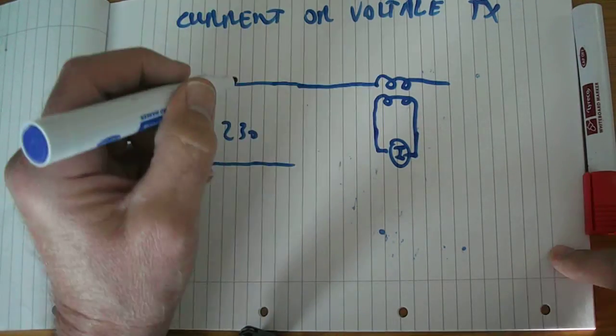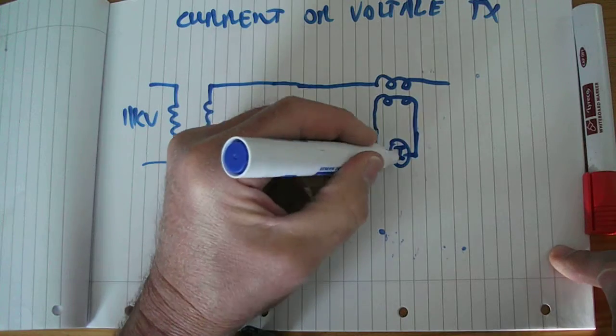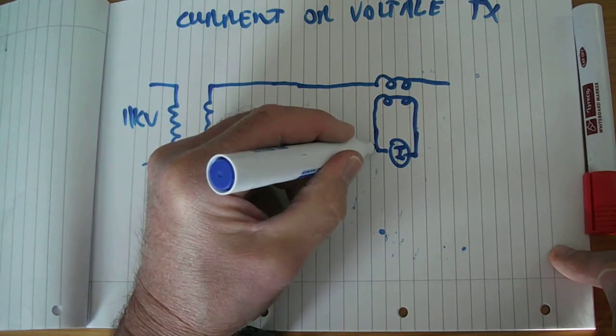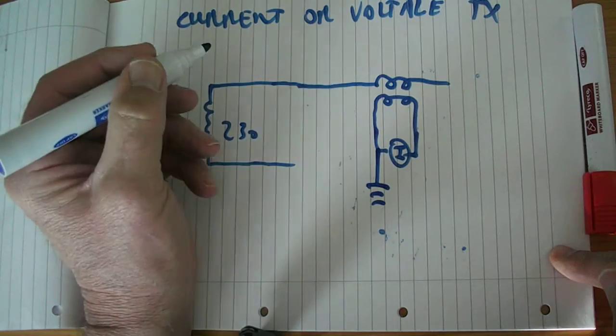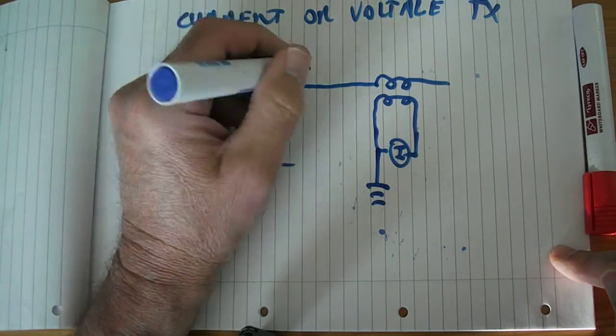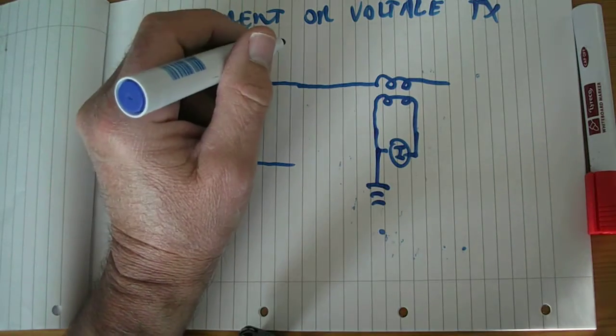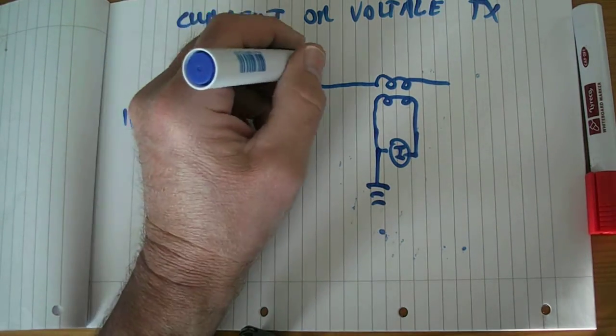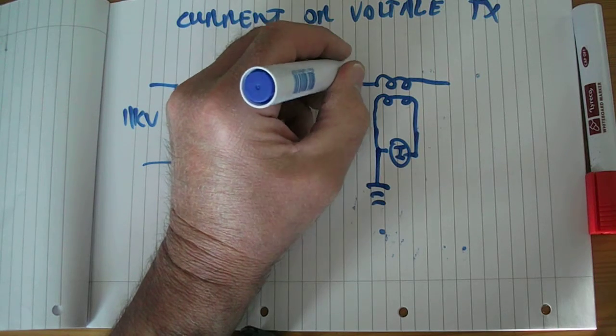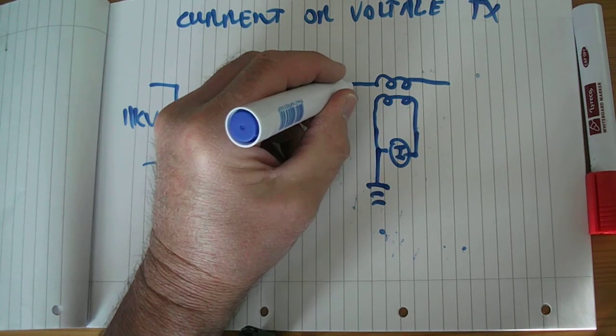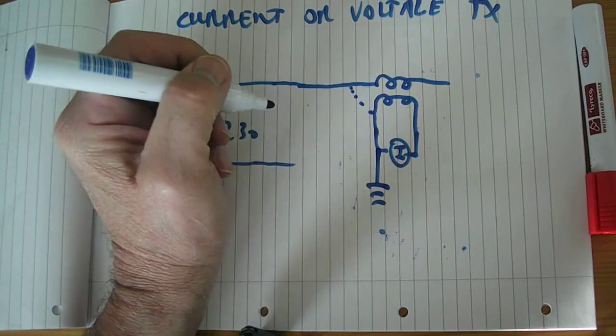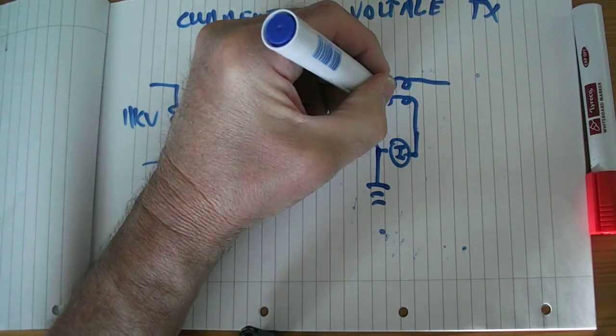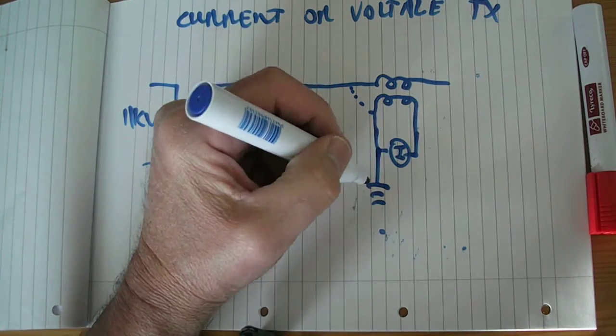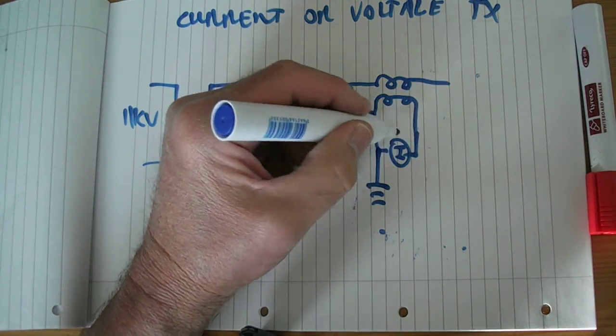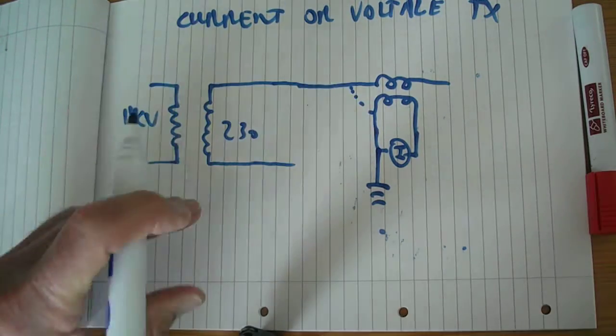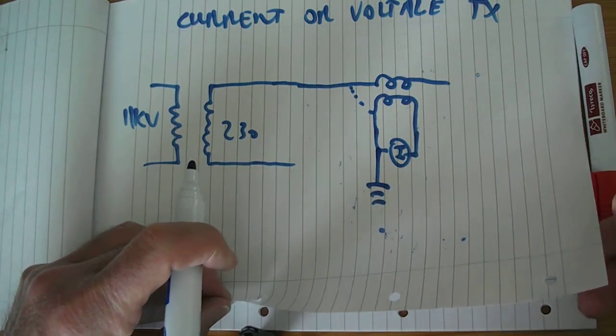But the important thing is, and you may get questions on this, is that this secondary on this current transformer has to be connected to earth on one side. The reason for that is because if there's a lightning strike or there's another fault on the line which produces arcing, then the voltage on this line could rise rapidly, and it could cause a flashover to the secondary inside this current transformer. So for safety reasons, to protect the equipment and to protect personnel who might be using this equipment, this side must be earthed. Okay, remember that one.